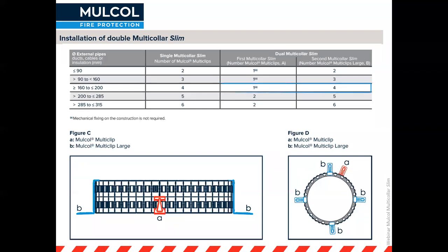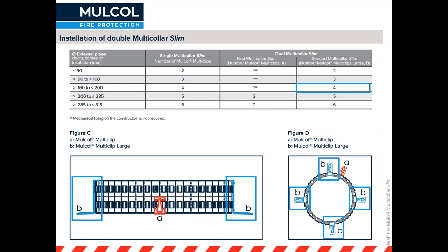For a pipe between 160 and 200 millimeters, you need just one multi-clip to join the Multicollar together to make it into a round shape, and you don't even need to mechanically fix this to the wall. The large multi-clips — the blue ones — you need four of them, and they will automatically hold the first collar in place. So you end up with a 60 millimeter combined height.